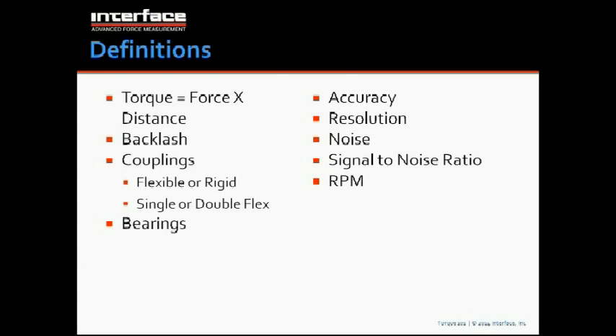Couplings are used to mount torque transducers into a drive line. Typically, they have to be flexible. Sometimes rigid couplings are used. Backlash is a feature that's typically undesirable in a drive line, and that has to do with some movement, say within the coupling in a shaft, where, when you reverse direction, you may get some slop in the connection. Bearings are used to support rotating elements and also to take extraneous loads.